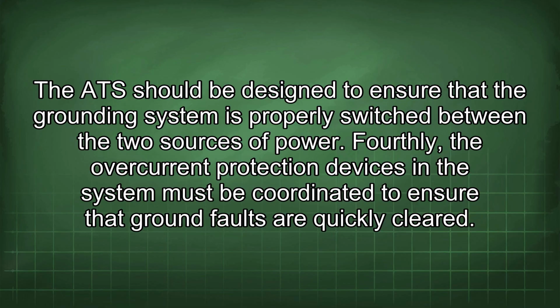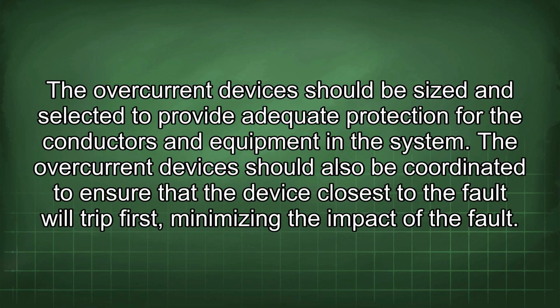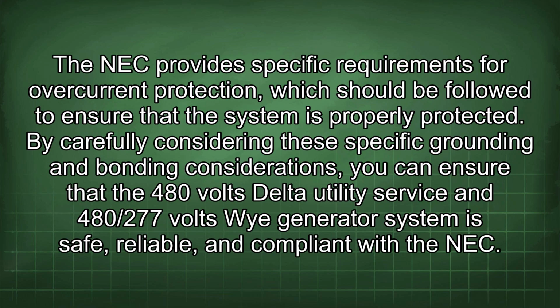Fourthly, the overcurrent protection devices in the system must be coordinated to ensure that ground faults are quickly cleared. The overcurrent devices should be sized and selected to provide adequate protection for the conductors and equipment in the system. The overcurrent devices should also be coordinated to ensure that the device closest to the fault will trip first, minimizing the impact of the fault. The NEC provides specific requirements for overcurrent protection, which should be followed to ensure that the system is properly protected.